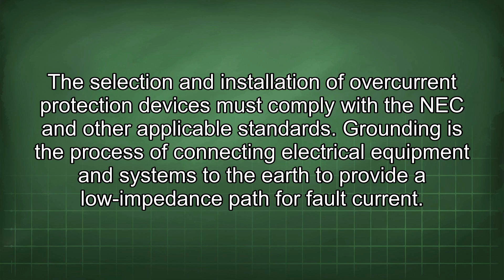Grounding is the process of connecting electrical equipment and systems to the earth to provide a low-impedance path for fault current. Grounding helps to protect against electric shock and equipment damage by providing a path for fault current to flow back to the source, causing the overcurrent protection device to trip and de-energize the circuit.